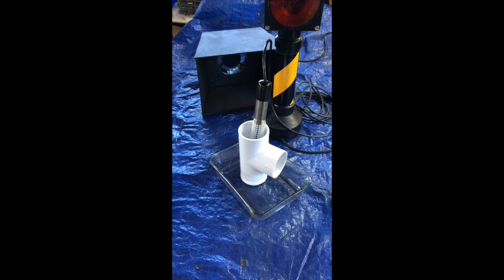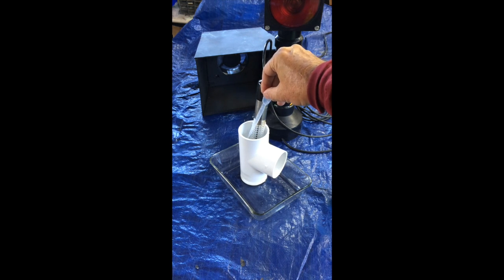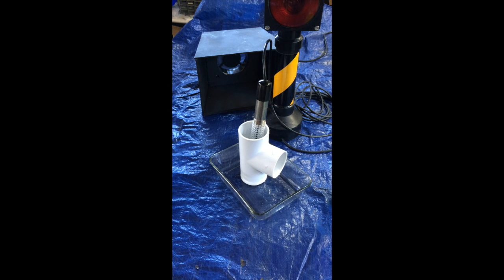And okay, we paused the video a bit there since it's not too exciting to watch nothing happen, but we're getting very close to the point where water is going to start to come out of the side of the T. So we'll finish the test, and water is just beginning to pour out of the side of the T. As we add more water, it's not going to get any higher in the fitting because it's coming out the sides. So that's the conclusion of phase 3, and what we've demonstrated is the ability to detect the West Virginia brine, also naphtha as a proxy for crude oil, and the fact that the sensor rejects tap water in this case, like it would rainwater or condensation.